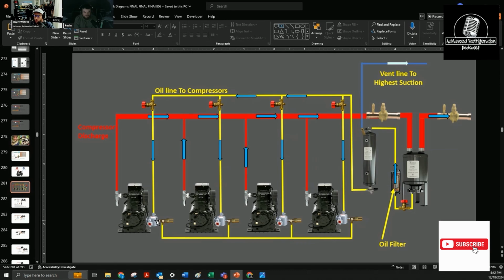Usually like 5 minutes? Even 10 minutes. Most compressors will hold oil; you could valve off that oil valve and that compressor would stay filled with oil, if no blow by, 35, 45 minutes, even an hour, I've seen. It depends how low your compressor is; 35 minutes is pushing it, I feel like. It depends on how hot it is too, because the higher the compression ratio, the more heat, the more oil it's going to use. So on a fall day, like winter in Texas, you could actually see it go 35, 45 minutes without emptying out.